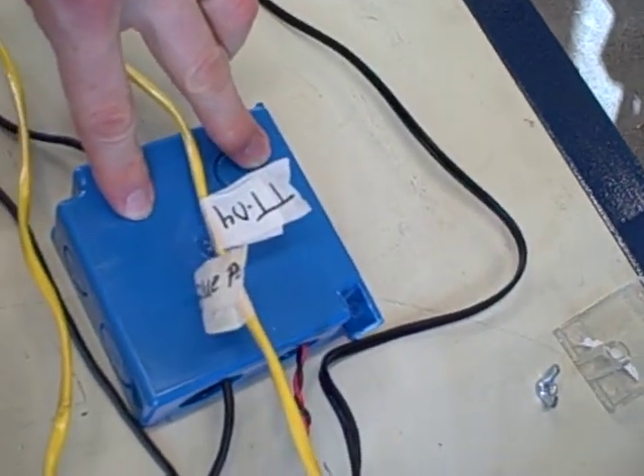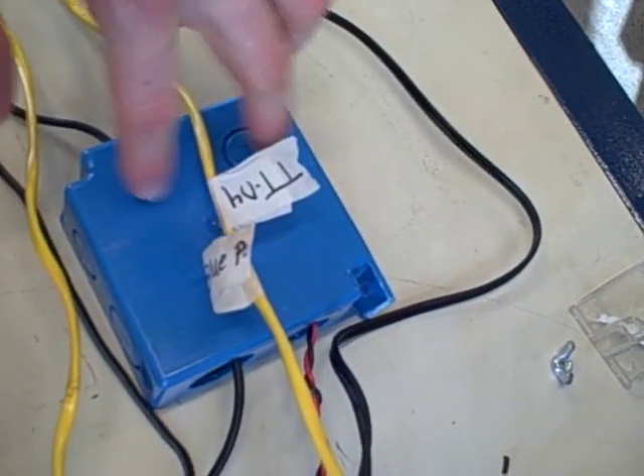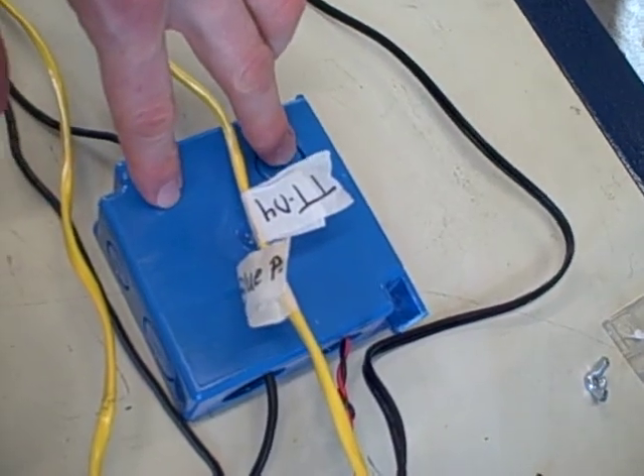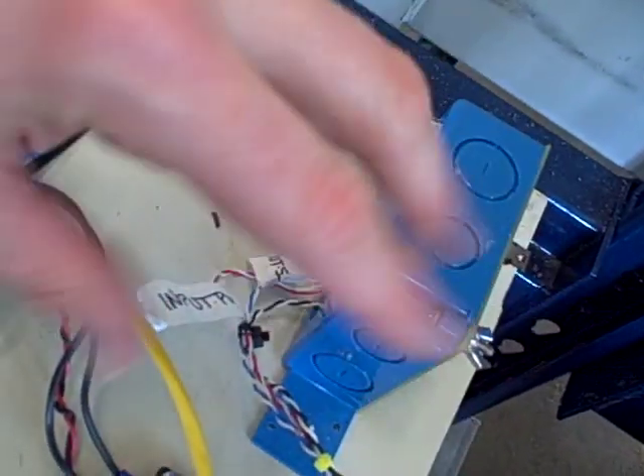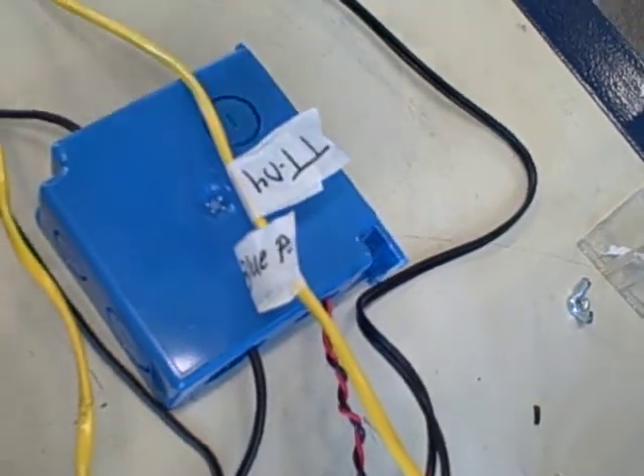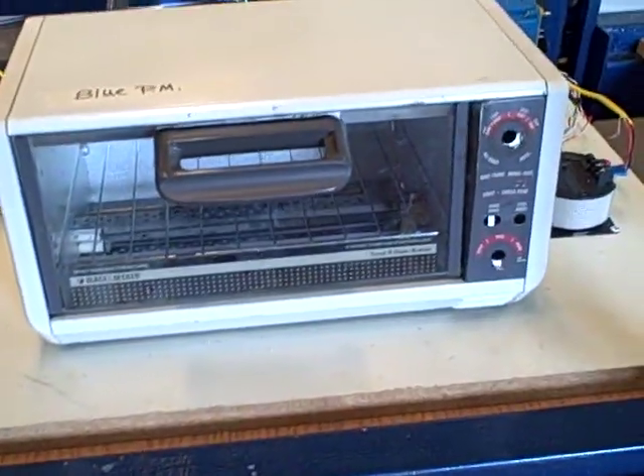Underneath here we've got a solid state relay that controls the power going to the heating element. So that PWM board simply pulses on and off, the relay switches the power on and off. That's the process itself.